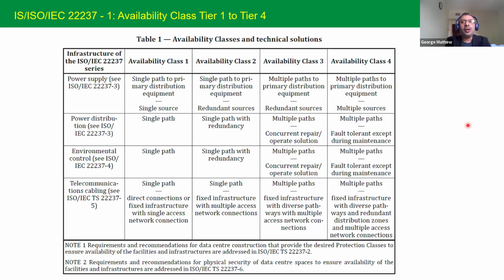So class 2 is on a single path for power and cooling. However, the equipment, which is the generator, chiller, and cooling equipment like a CRAC unit or fan wall unit, is configured with n plus 1. So when there is a failure of a chiller, we can have the standby chiller, or the plus 1 chiller, on, and the system can continue. This is class 2. Now, our life is a bit easier in class 3.